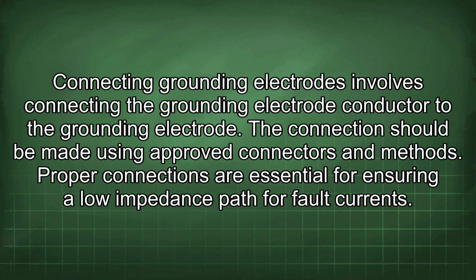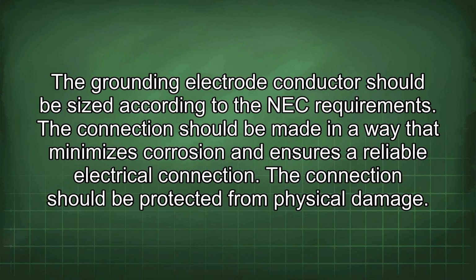Connecting grounding electrodes involves connecting the grounding electrode conductor to the grounding electrode. The connection should be made using approved connectors and methods. Proper connections are essential for ensuring a low impedance path for fault currents. The grounding electrode conductor should be sized according to the NEC requirements. The connection should be made in a way that minimizes corrosion and ensures a reliable electrical connection. The connection should be protected from physical damage.